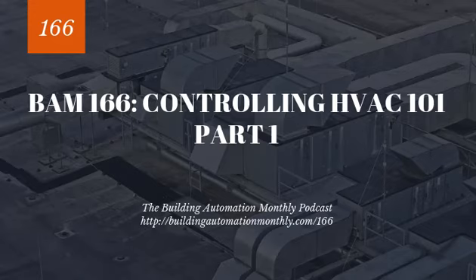But you could control via minimum damper position. You could control what's called your economizer in your outdoor airflow. That mixes a certain amount of outdoor airflow into the return air stream, considering that this is a mixed air, not 100% outdoor air unit. And so you're going and you're providing this air. That's one way to do it. The other way is based off CO2 control, where you reset the damper to drive to control CO2.